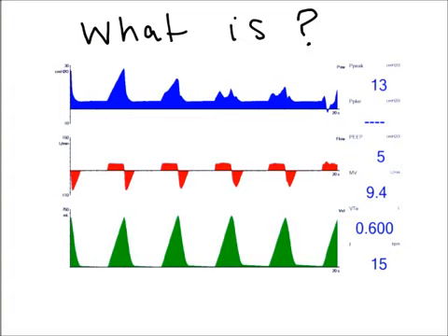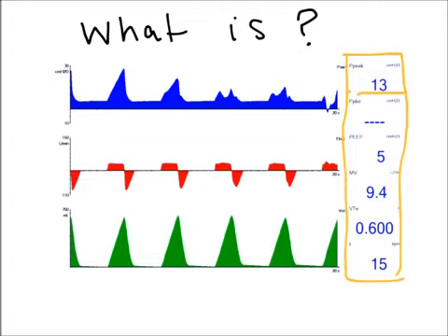We're going to look at this ventilator screen and we can see the waveforms and the measured values to the right of the screen. Here are some measured values. My plateau pressure is a measured value. I have my peak pressure, and below that is a plateau pressure. As you notice, it's just dashed out.